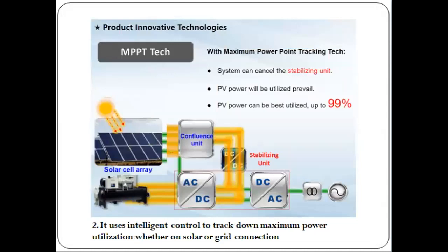Number two, it uses intelligent control to track maximum power utilization, whether on solar or grid connection. MPPT, or Maximum Power Point Tracking Technology, is used to deal with the unstable voltage of photovoltaic power. With MPPT control, combined with AC and DC commutation technology, the system doesn't need the AC-DC constant voltage modulation that a traditional photovoltaic air conditioner would need. Actually, it can track and control the real-time photovoltaic power generation to its maximum so that photovoltaic power can be best utilized by the centrifugal chiller.